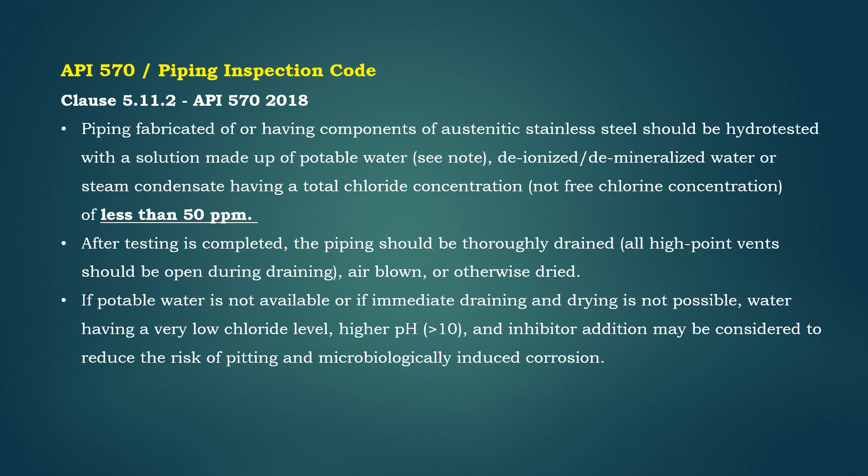Piping fabricated of, or having components of, austenitic stainless steel should be hydro-tested with a solution made up of potable water, deionized or demineralized water, or steam condensate having a total chloride concentration of less than 50 ppm. After testing is completed, the piping should be thoroughly drained, air blown, or otherwise dried.